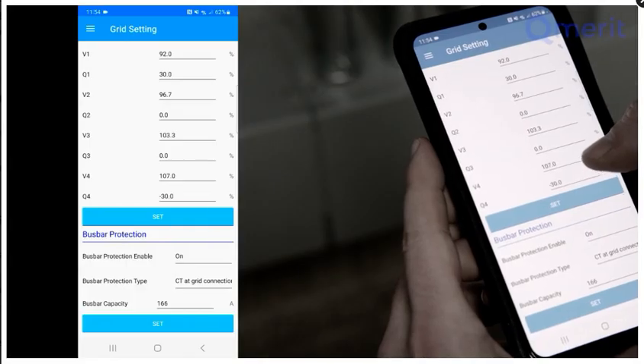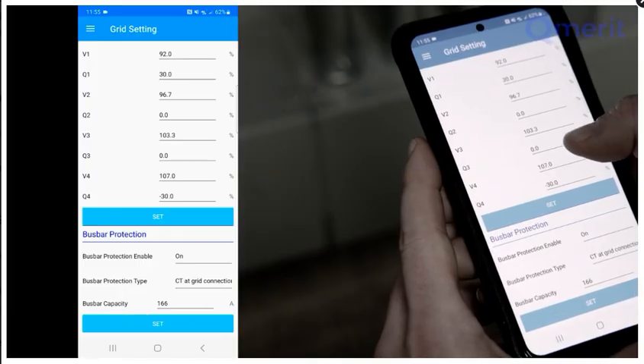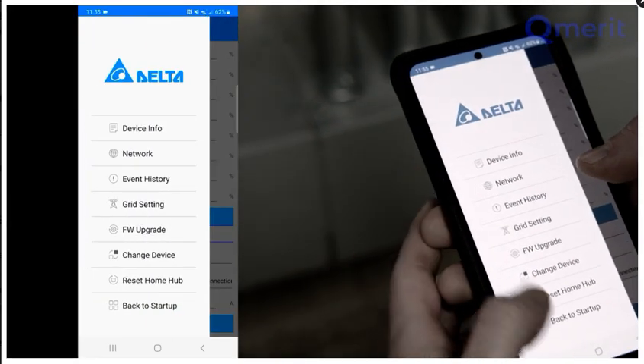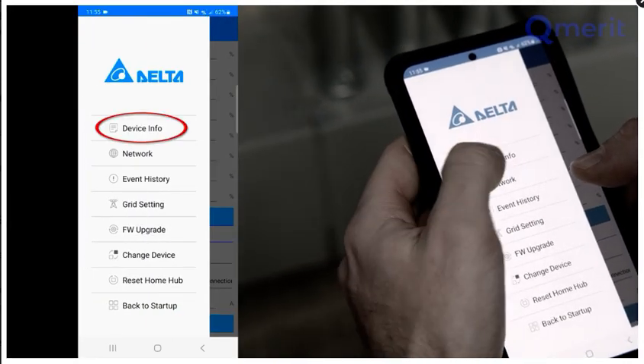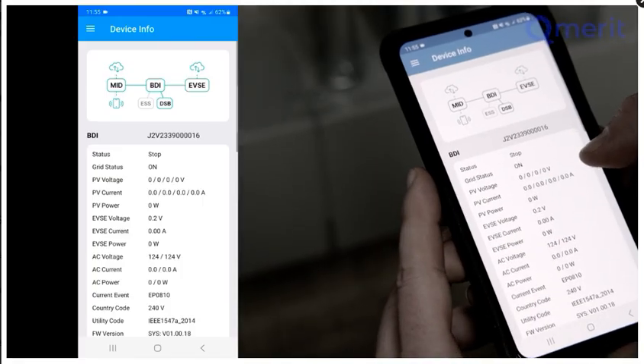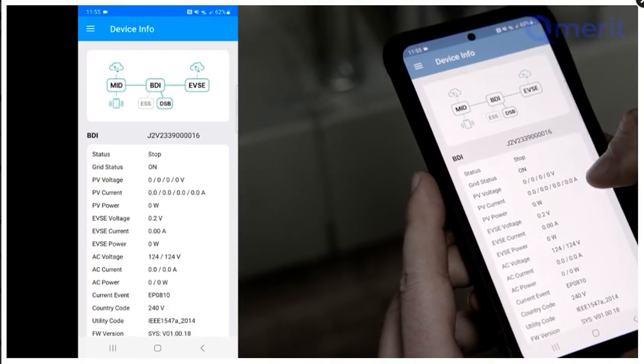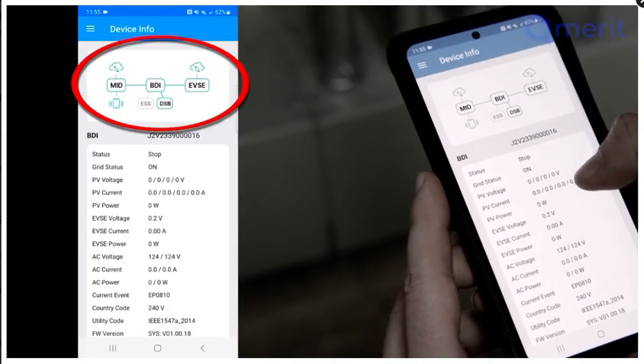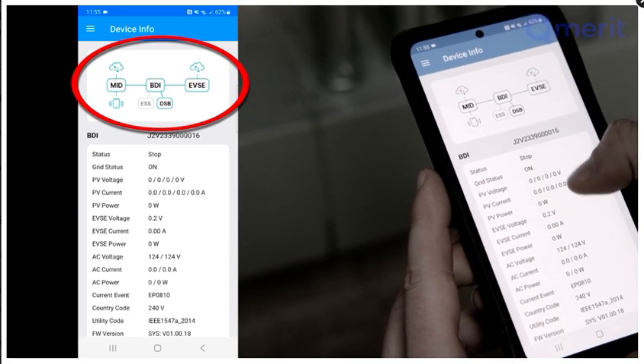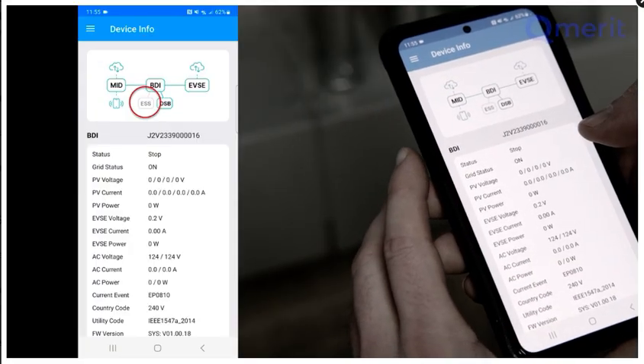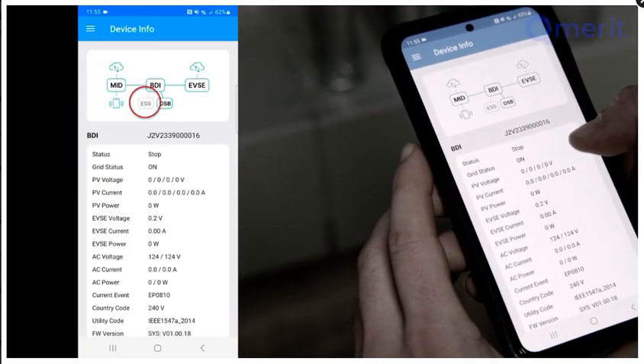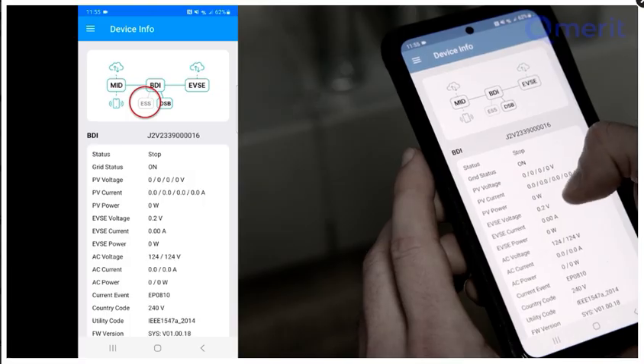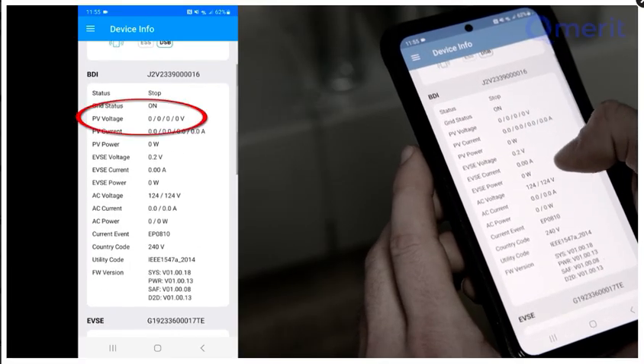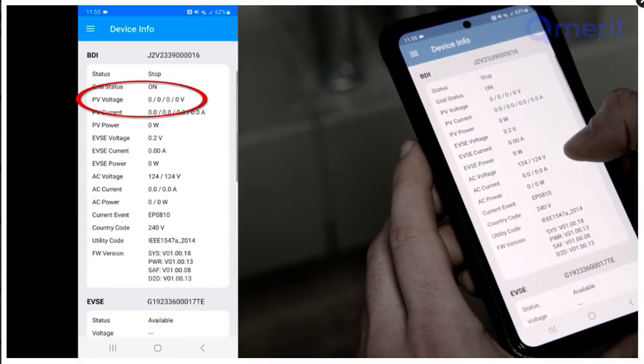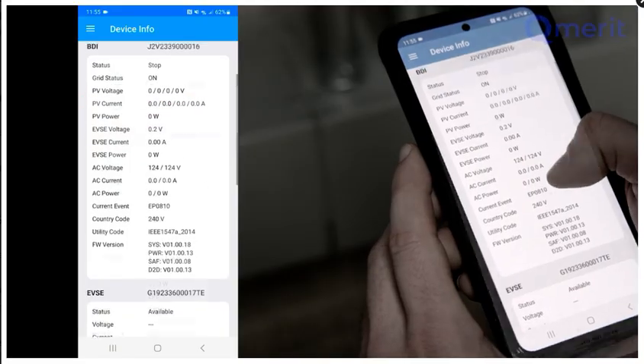Select Yes to review your settings. Select the menu icon at the top left. Select Device Info. Check to see if all the devices are connected. The cloud icons must be green to show connectivity. If gray, go back and do the recommissioning process. ESS is grayed out because there is no stationary storage connected in this installation. PV voltage is 0 because there is no solar attached to the system as well.